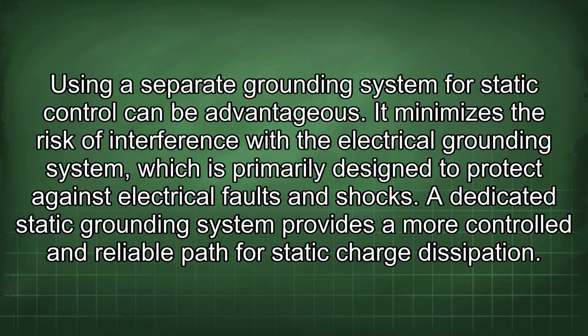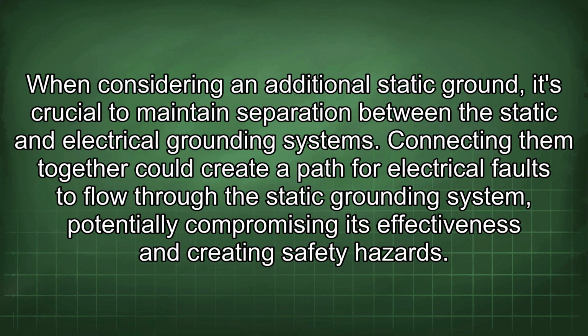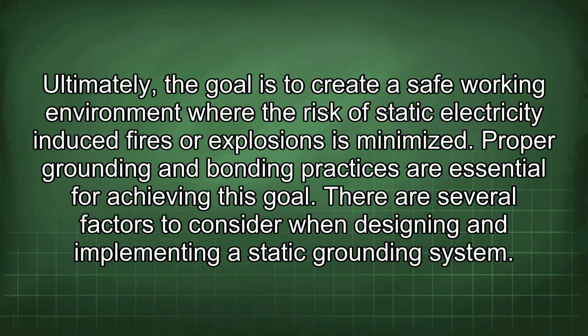Using a separate grounding system for static control can be advantageous. It minimizes the risk of interference with the electrical grounding system, which is primarily designed to protect against electrical faults and shocks. A dedicated static grounding system provides a more controlled and reliable path for static charge dissipation. When considering an additional static ground, it's crucial to maintain separation between the static and electrical grounding systems. Connecting them together could create a path for electrical faults to flow through the static grounding system, potentially compromising its effectiveness and creating safety hazards. Ultimately, the goal is to create a safe working environment where the risk of static electricity-induced fires or explosions is minimized. Proper grounding and bonding practices are essential for achieving this goal.